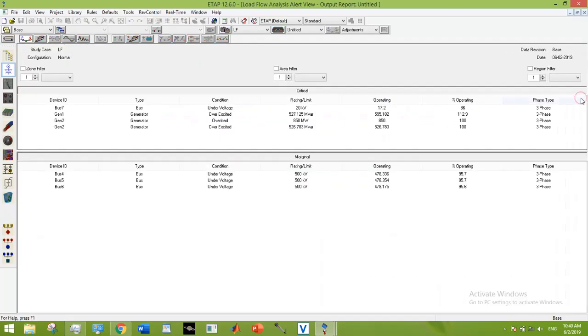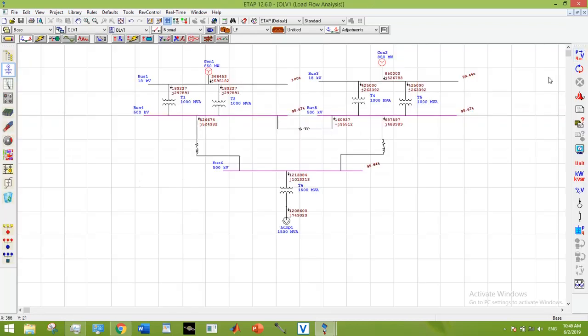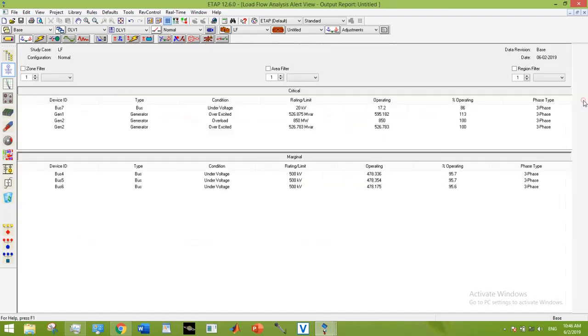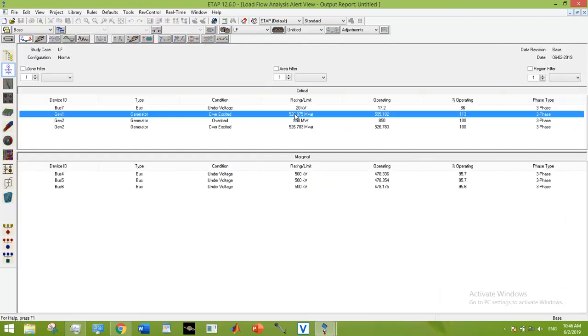First I am going to deal with the overexcitation issue in Generator 1. Here you can see the generator VAR limit was 526.87 MVARs and its operating VAR is 595.18 MVARs.